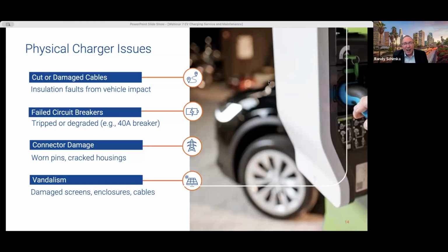First up, we have cut or damaged cables. This can happen from vehicle impact or wear or vandalism and can lead to wires getting broken or insulation faults. Regular inspection can spot frayed cables or exposed wires before they can cause charger outages. Next, let's look at intermittent or failed circuit breakers. These mechanical devices might trip frequently or degrade over time, which would cut power to the charger. Routine testing ensures that breakers are functioning correctly and should minimize any unexpected shutdowns.